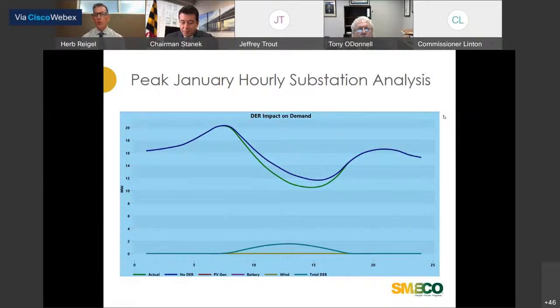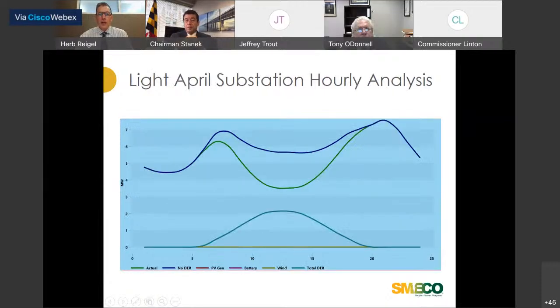So this is a representative example of what it looks like during a January month. Moving to the next slide, this shows what the same station might look like during a lighter load period in April. We see the same thing, two humps, one in the morning and one in the evening, but the system peak load on this station has dropped from 20 megawatts to almost 7 to 7.5 megawatts. Because we're looking at April, the amount of solar generation capacity is a little higher than in January, and extends a bit longer because daylight hours are getting longer. If we overlay those two curves, you can see the resultant load shape for this circuit.